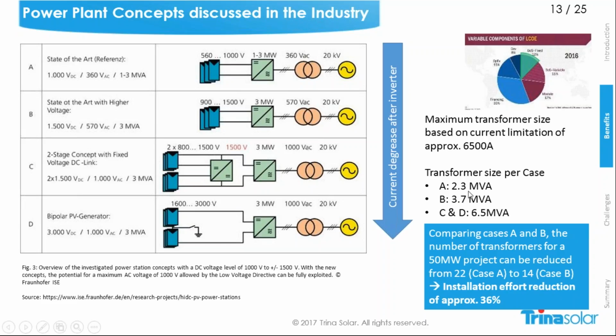If I now take a look at a utility scale project, for example, if I have a 50 megawatt project and only compare case A and B, those are the upper two, then in case A 22 transformers are required, in case B only 14. That means that the installation effort can be reduced by approximately 36%, which is a clear benefit, especially if you have extremely large systems.